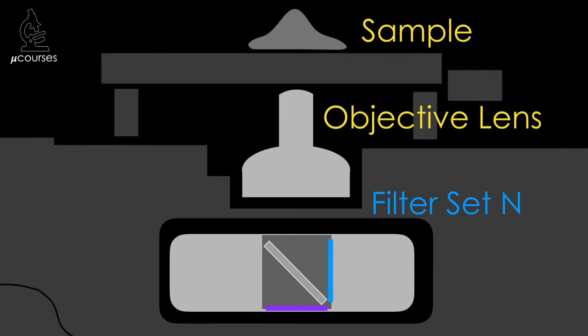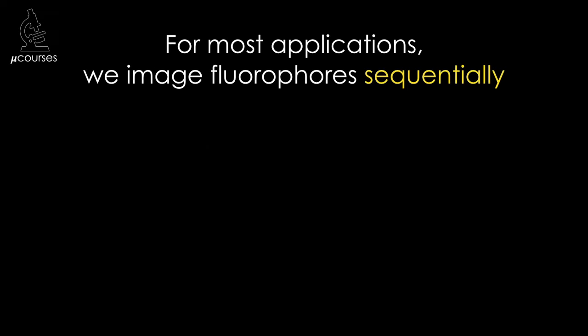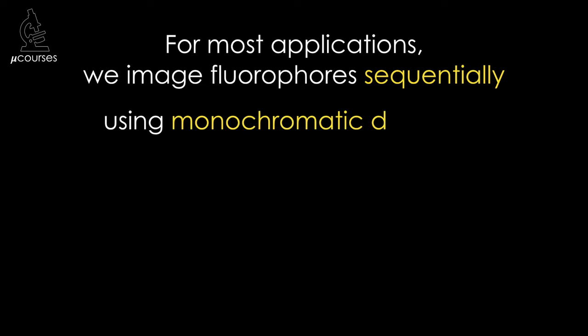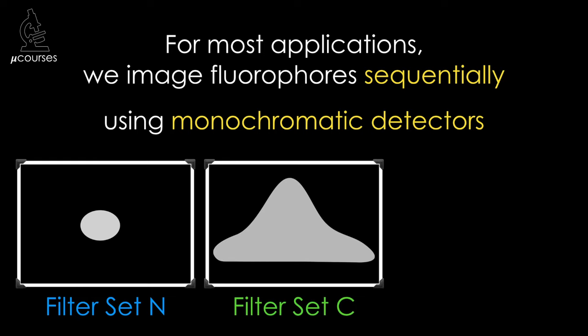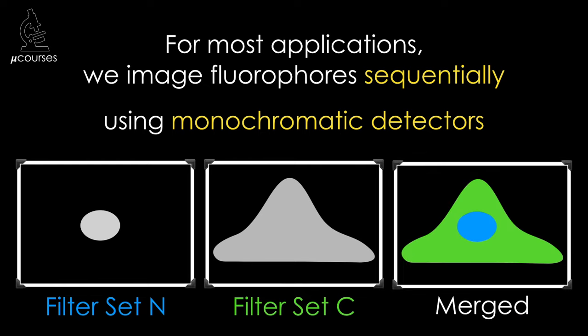Imaging multiple fluorophores in the same sample is most commonly performed sequentially by switching between filter sets in the microscope. For the vast majority of fluorescence applications, we acquire images sequentially and use monochromatic detectors because they're the most sensitive. In our example, we would acquire a monochromatic image with filter set N, then switch to filter set C and acquire a second monochromatic image. If we'd like, we can then digitally pseudocolor and merge these two images into one to aid in visualization of relative localization.